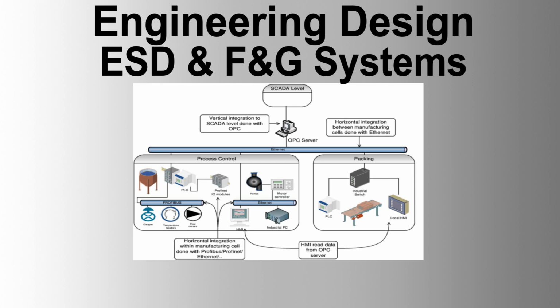Redundancy and reliability. 1. High availability. The power supply system must be designed with redundancy to ensure high reliability and availability of the ESD F&G system. Redundant power supplies must automatically take over in case of a primary power supply failure without any manual intervention. 2. Maintenance and testing. Regular maintenance and testing procedures must be established to ensure the power supply system remains in optimal condition. Scheduled battery replacements and UPS system checks must be part of the maintenance plan.